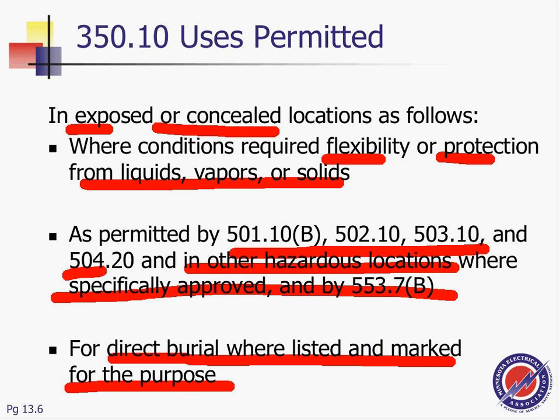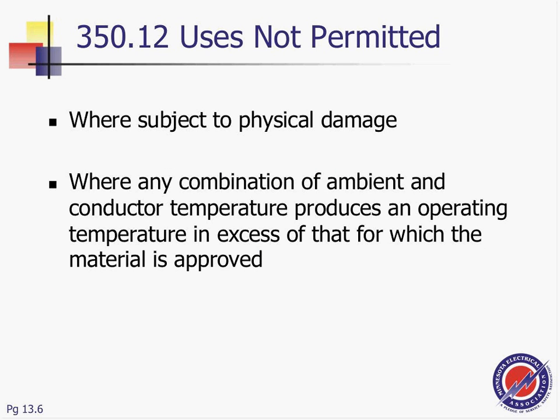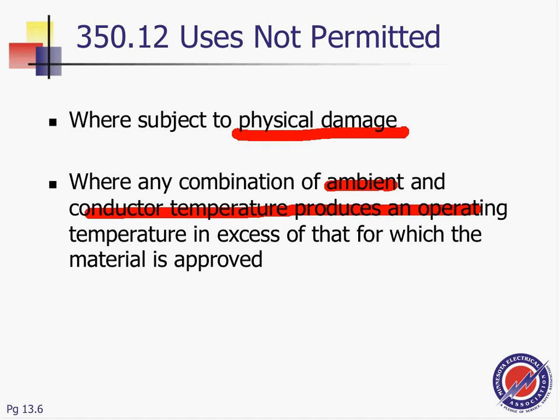Advantage: you can get them listed to be directly buried. You put them in a flexible location where you need flexibility and a wet location because of liquids and so forth. The same thing, guys: subject to physical damage. You don't want to use it in a place where it's subject to physical damage. And another thing, where the combination of the ambient temperature and conductor produce an operating temperature in excess of which the material is approved for.